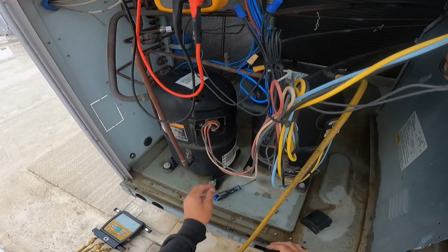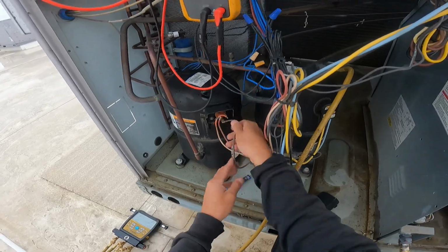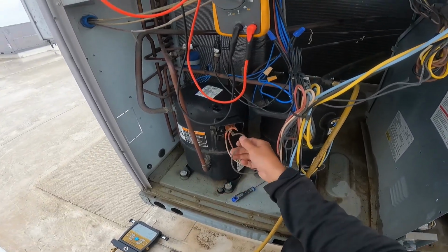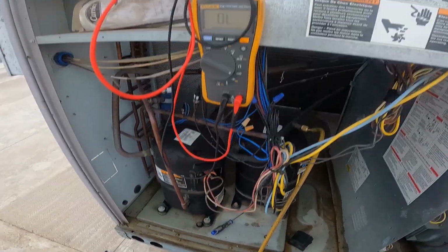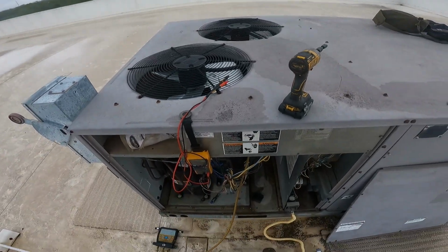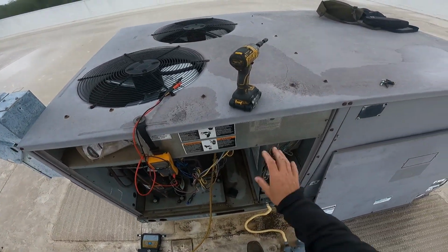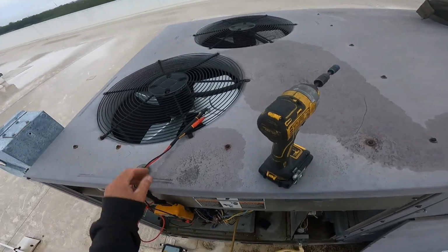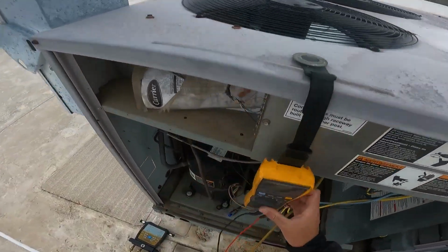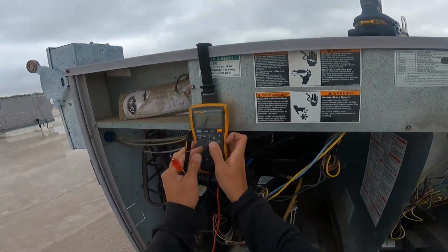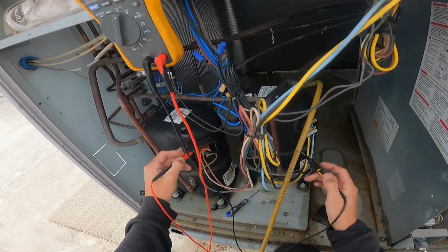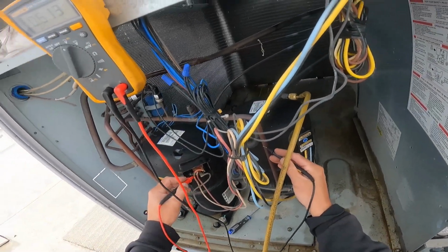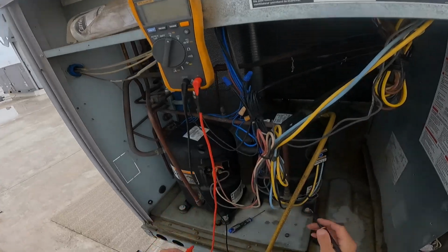All right, we're going to check this. All we've got to do is pull off two of the leads. But this thing's under power, right? So it's under power, but the contactor shouldn't be pulled in. Just for giggles, I'm going to make sure I'm not getting any voltage to any of these lines - I'm not trying to get shocked. That's got 280 on it.